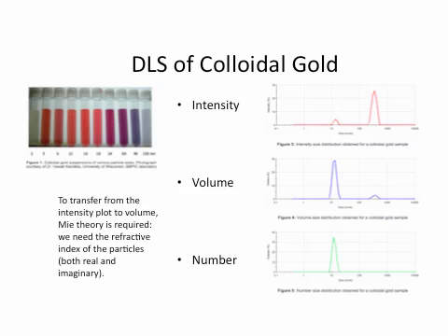So what DLS does, it measures the intensity profile. So you'll see here in this picture, you have a little bit of intensity at about 10, 15 nanometer, and you see some peaks here on the logarithmic scale at about 200 nanometer. Yeah? And if you go from intensity to volume, so you go from diameter to the power 6 to diameter to the power 3, you divide by diameter to the power 3, suddenly you see per volume you have way more small ones than large ones.